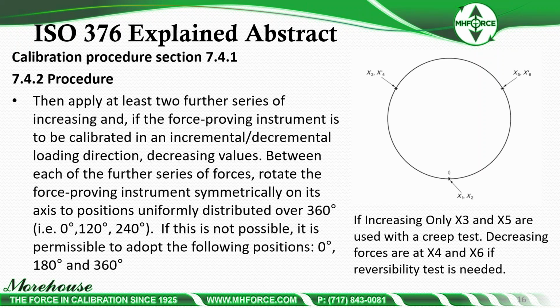Then we're going to apply 2 further series of increasing, and if the force proving instrument is to be calibrated in incremental, decremental loading directions, decreasing values. Between each of the further series of forces, rotate the force proving instrument symmetrically on its axis to positions uniformly distributed over 360, namely 0, 120, 240. If this is not possible, it is permissible to adopt the following positions, 0, 180, and 360. So basically here, we're going to move the instrument.